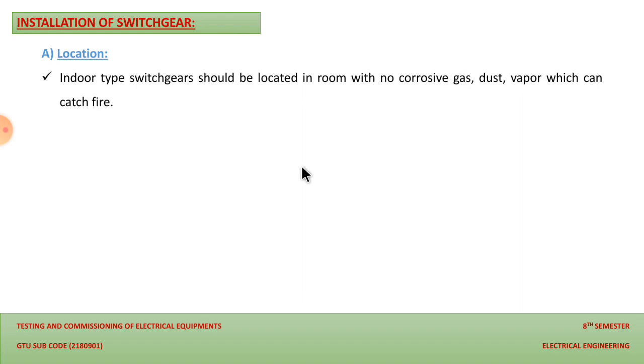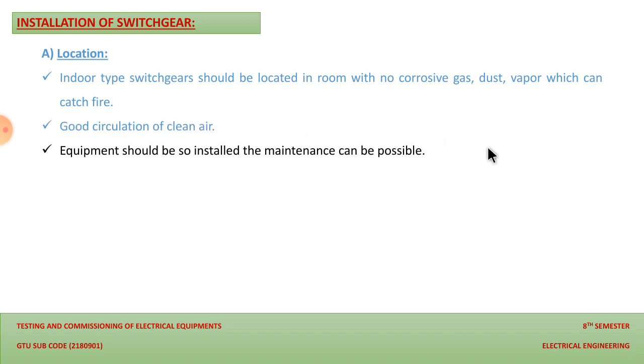So, location. Suppose we are using our device indoors: an indoor type switchgear should be located in a room with no corrosive gas and no dust or vapor which can catch fire. This is the point we should keep in mind where we are locating our transformer at the consumer premises. And good circulation of clean air is required for natural air cooling of the switchgear while operating. And the equipment should be installed so that maintenance is possible. In future maintenance is necessary, so we should keep a specific distance for it.